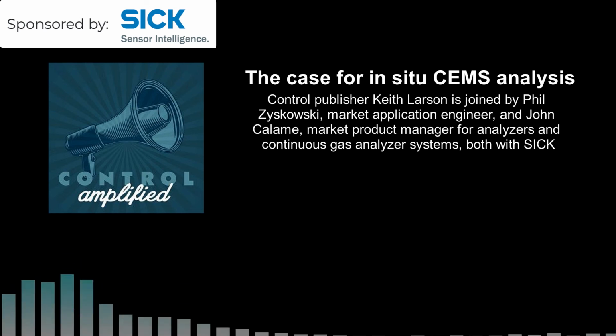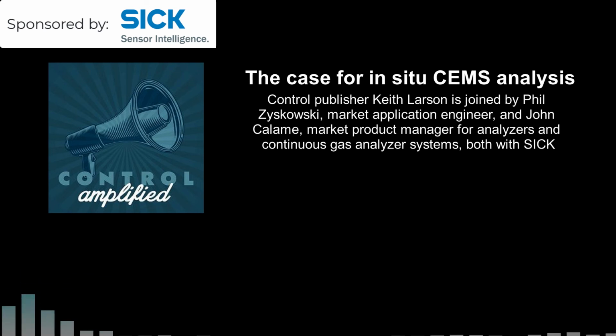But in the other industries, we've incorporated, and it's in all of our in situ analyzers, a series of internal optical filters. And so Part 60, for example, it's an EPA regulation as well, but it does allow the use of the manufacturer's suggested optical calibration filters as your daily calibration. So you do not have to use calibration gas on a daily basis. You've still got to check the analyzer on a quarterly basis with calibration standards, but there's savings there for sure, and a lot less maintenance if you can get by with just using the optical filters. Makes a lot of sense, really does.